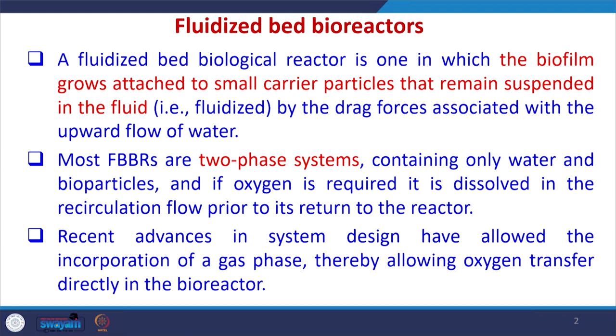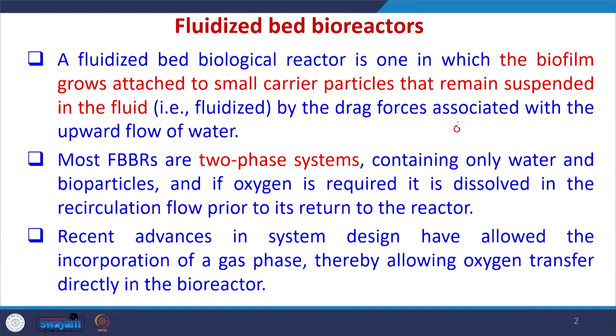A fluidized bed biological reactor is one in which the biofilm grows attached to a small carrier particle that remains suspended in the fluid, which is actually fluidized by the drag force associated with the upward flow of water. So in this reactor, the biofilm is grown on a small carrier particle, which is suspended in the reactor containing the wastewater to be treated. This is the fluidized bed reactor.